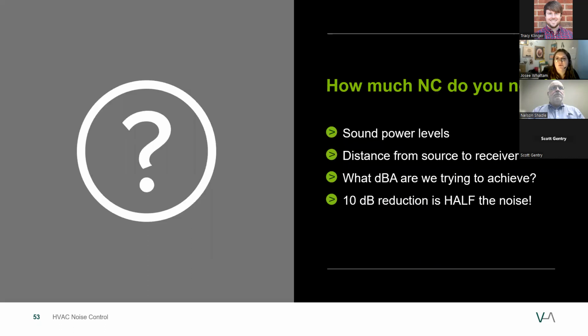But how much noise control do you need for outdoor noise issues? The answer is similar to the indoor noise issues that we discussed earlier. You would need to know the source's sound power levels, the distance from the source to the receiver, and what dBA to achieve. The units used in environmental noise are A-weighted sound pressure levels to approximate what the human ear will hear. A distance measurement is important as well because of the inverse square law of sound. So sound traveling twice the distance will be perceived at 6 dB lower. A last thing to keep in mind is that a reduction of 10 dB is actually reducing the noise in half due to logarithmic laws.